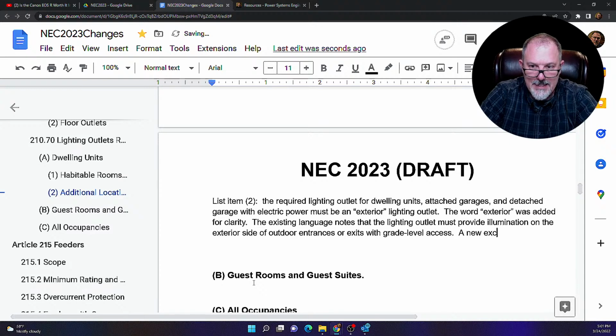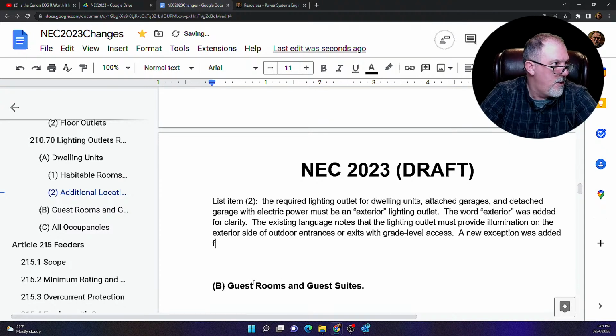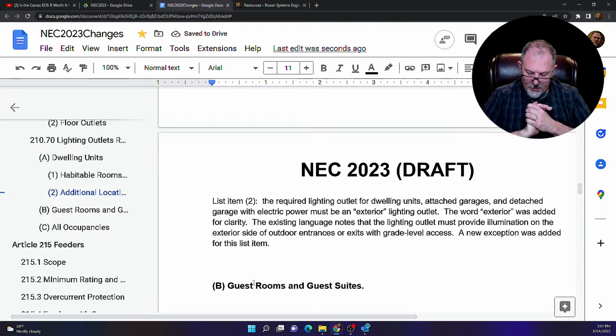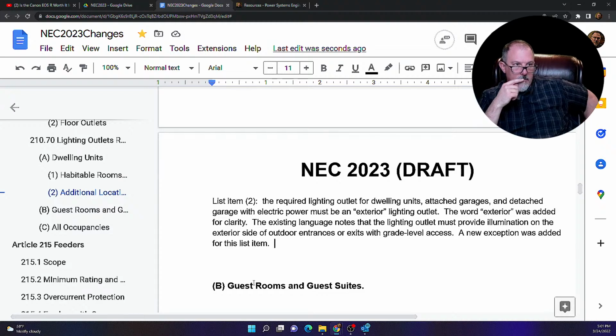A new exception was added for this list item. And what it says, is it new? Exception 2, for an outdoor grade level sloped bulkhead door. For an outdoor grade level bulkhead door with stairway access to a subgrade level basement, the required lighting outlet that provides illumination on the stairway steps shall be permitted to be located in the basement interior within 5 foot horizontally of the bottommost stairway riser. This interior lighting outlet shall be permitted to be controlled by a listed wall-mounted control device or by a unit switch of the interior luminaire or interior lamp holder.